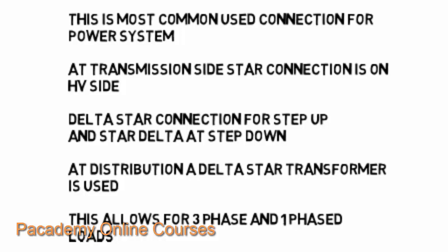At distribution level, a delta-star connection of transformer is used. This allows for three-phase and one-phase loads. The three-phase loads can be directly supplied to large industries, while the single-phase loads can be used for distribution to domestic households where single-phase equipment are used.